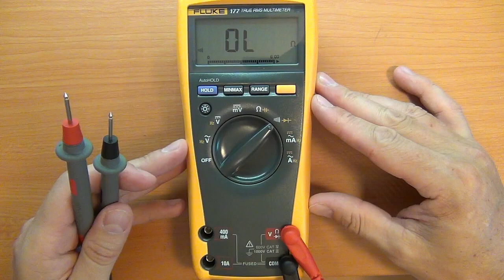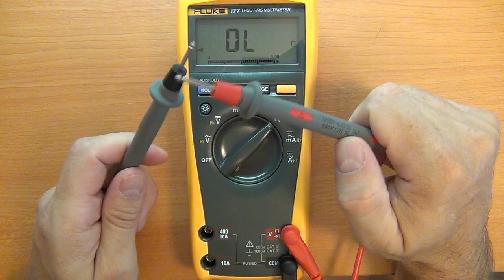Now I want to highlight one handy feature on a Fluke, which, if you look at my multimeter reviews, is something the Flukes are renowned for. The one thing to do is always check that your meter is working correctly. Hold your two leads together and make sure you get a good response, so that if your battery or something's wrong with your leads or your meter, you don't suddenly get results you don't want.